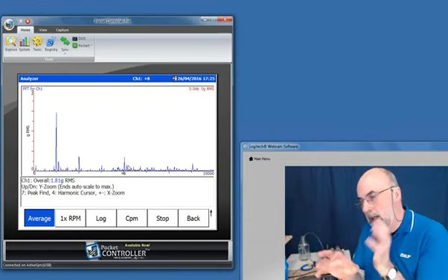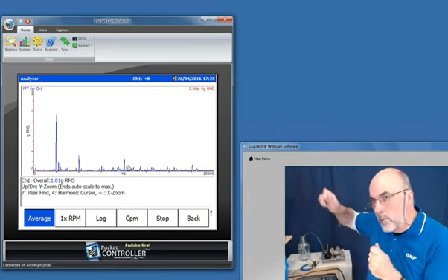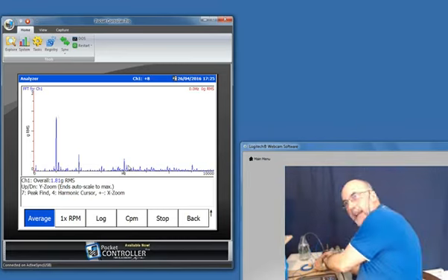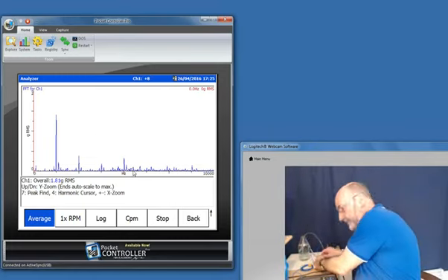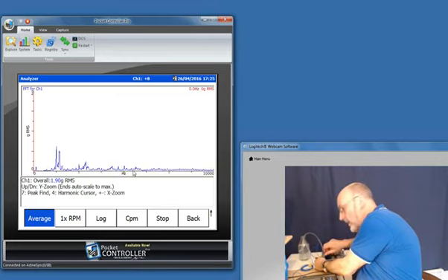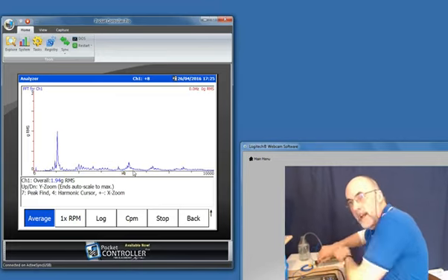That picture is moving. And what that allows me to do is roam with my accelerometer, where I'm going to increase the cavitation. And you should see the carpet level come up. We'll give that a whirl. There we are. We've made a change.